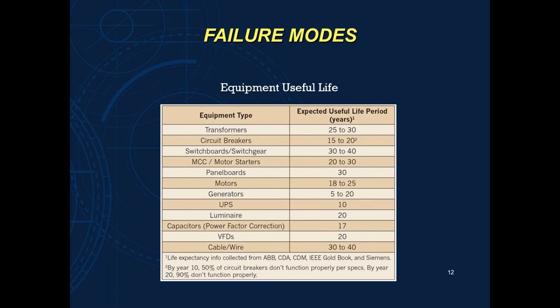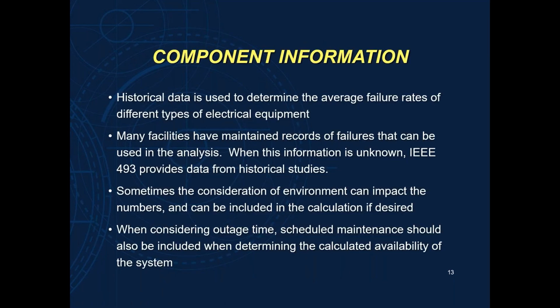These values may be averages taken off of real historical data, but if you provide proper maintenance, you can make sure that you're on the higher end of those values. So there's a lot of room for component failure out there in our electrical designs today. Historical data is typically what you're looking for.